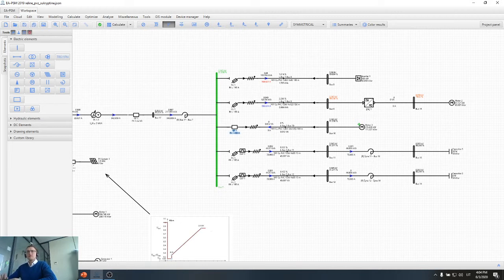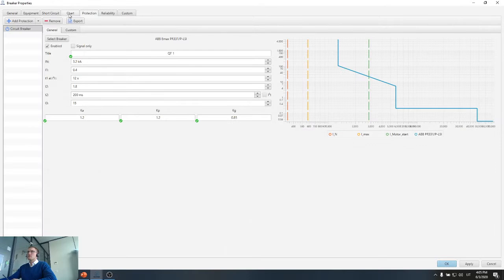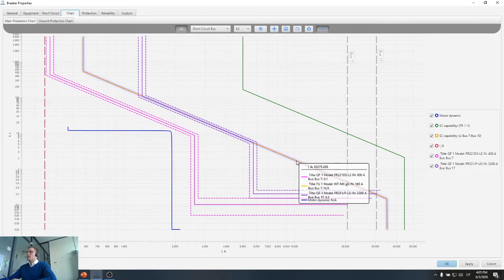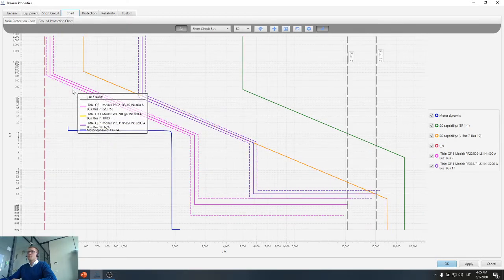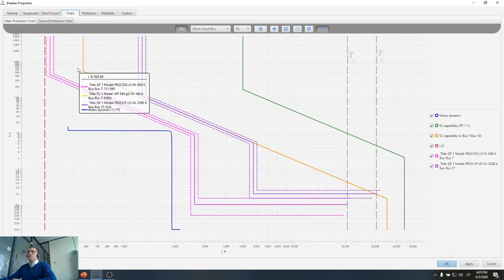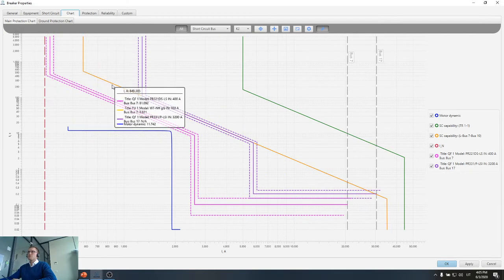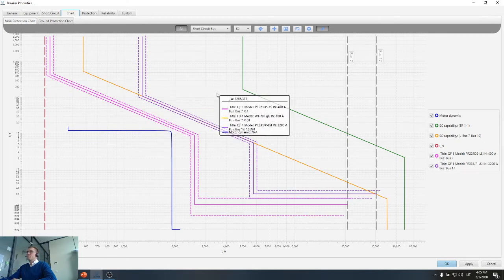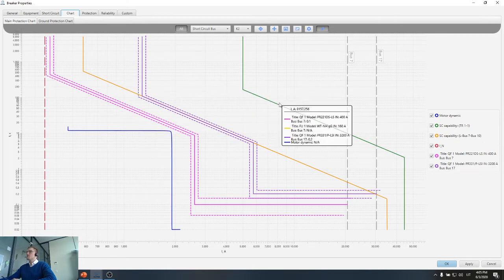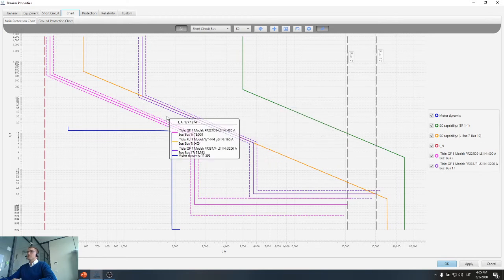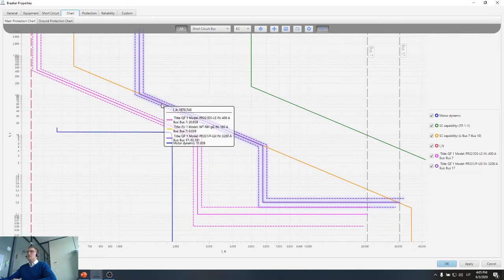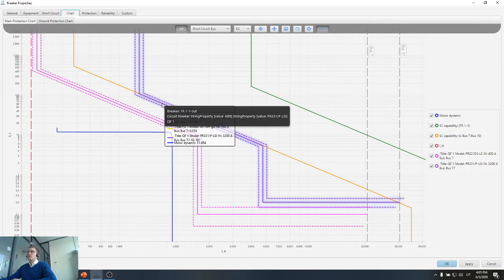Next question, is it possible to show the cable capability in the TCC curve so we can see if primary protection fails, whether backup protection detects it? So definitely, when we open TCC curves, we can see the cable capability. This is the breaker. This is the cable which is protected by the breaker. And basically this is our transformer. So we can see that our backup protection is not fully protecting our cable.